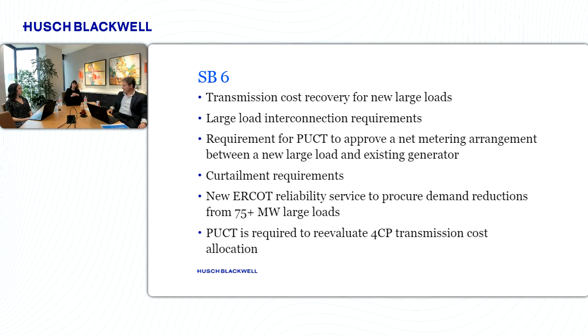There are also curtailment requirements and requirements to install equipment so load shed can be effectuated for new and expanded large loads. There's a provision to establish a new ERCOT reliability service to procure demand reductions from large loads of 75 megawatts or greater. And very importantly, the PUC is directed to reevaluate 4CP transmission cost allocation—that's going to be major.